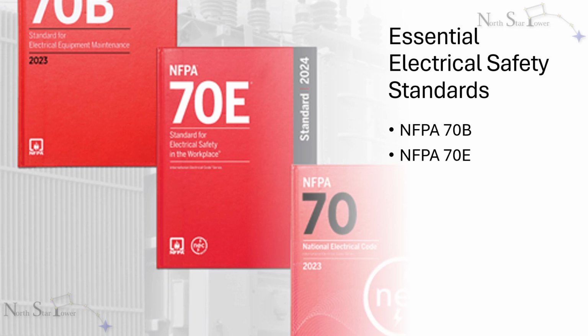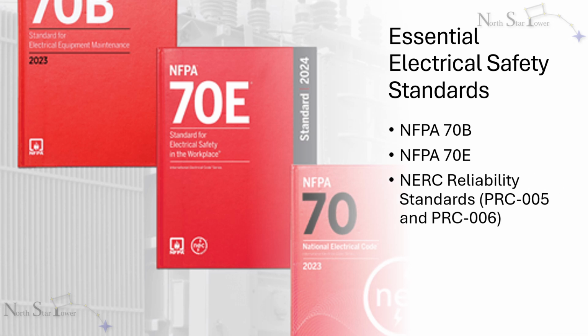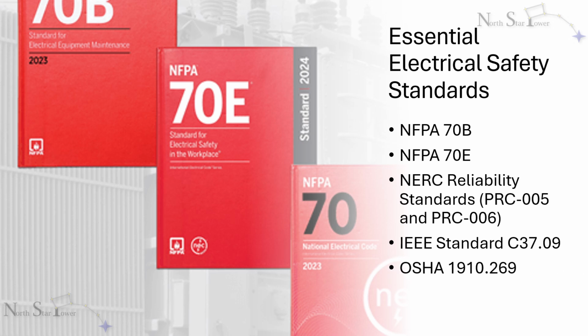detailed hazard analysis. The NERC reliability standards, PRC 005 and PRC 006, are mandatory for power generation and transmission facilities. These focus on integrity of systems critical to the electric grid. IEEE Standard C37.09 provides comprehensive procedures for verifying the operational and safety performance of electrical equipment, including dielectric, mechanical, and thermal evaluations. Finally, OSHA 1910.269 requires that electrical systems be maintained in safe operating condition, with testing and maintenance forming a cornerstone of workplace safety compliance. The common thread across all of these standards is clear. Electrical equipment must be routinely assessed, documented, and maintained.